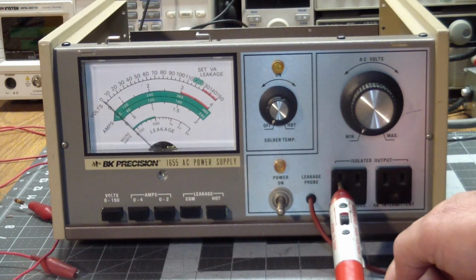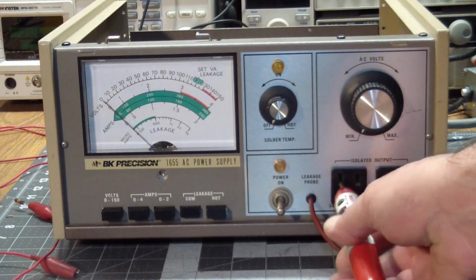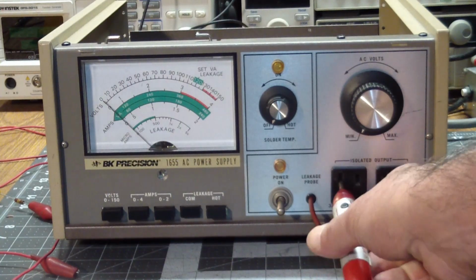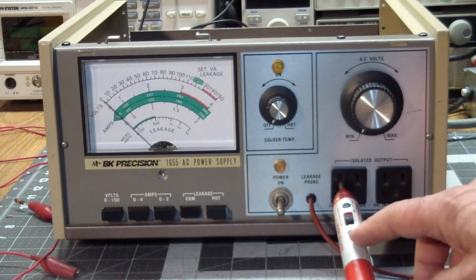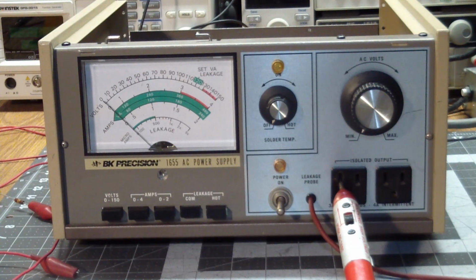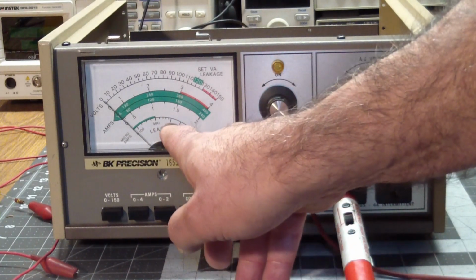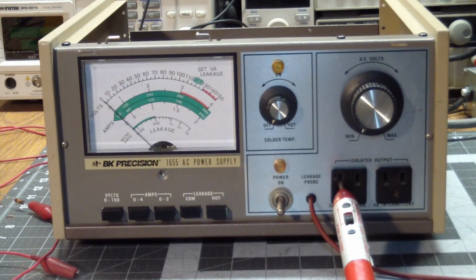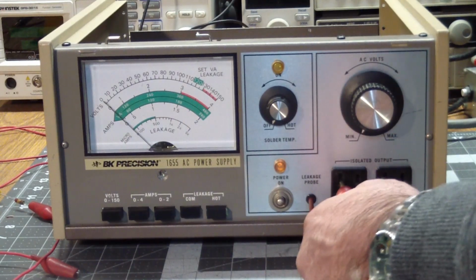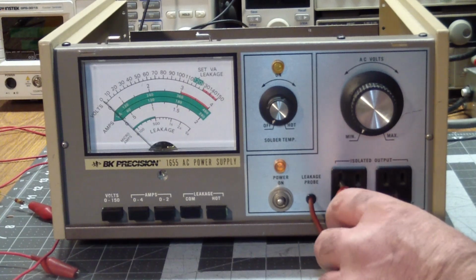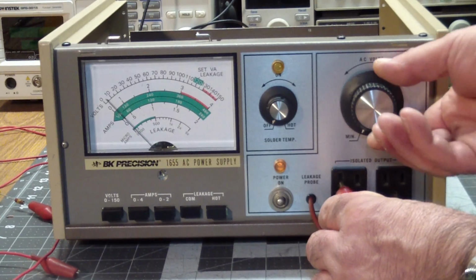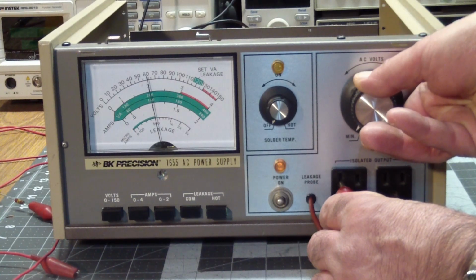Of course, what it took me a while to figure out is you actually have to slide this button forward to test. So I'm sitting there trying stuff, nothing's happening, but you have to turn the probe on. Select the leakage function and slowly increase the AC volts control until the meter reads 500 microamps on the leakage scale. The leakage scale's down here, and the green area is basically the leakage current. So we got this thing at 0, we turn it on, and then what we got to do is press this button and then turn the dial until we're at 500.